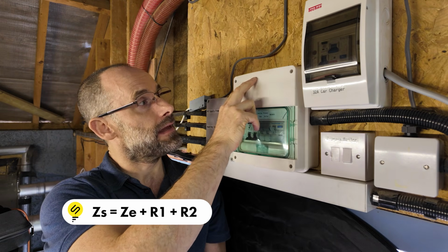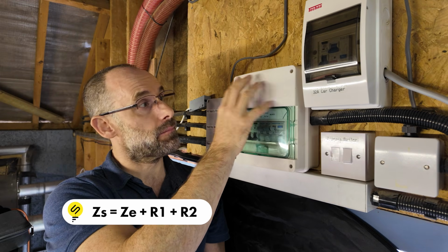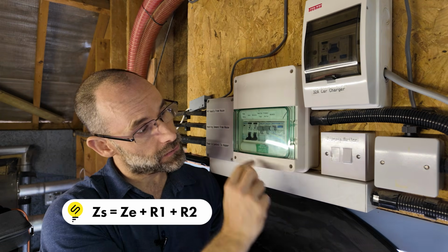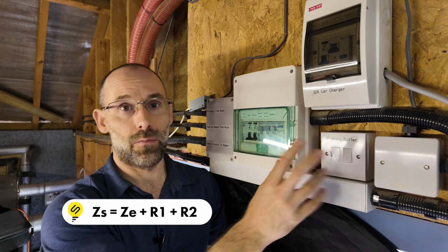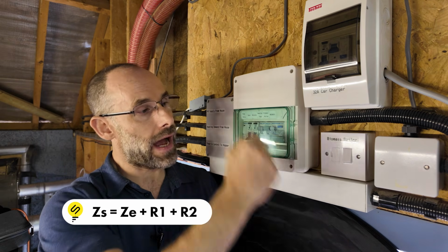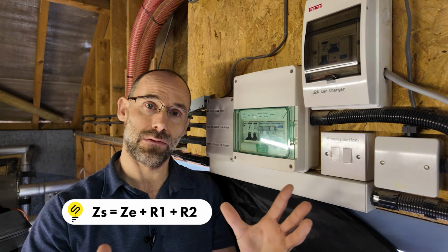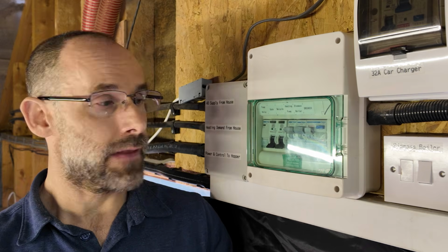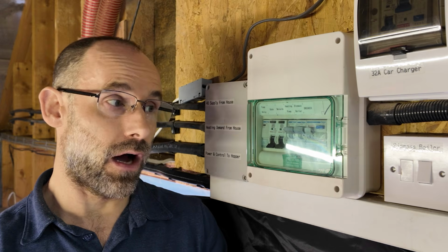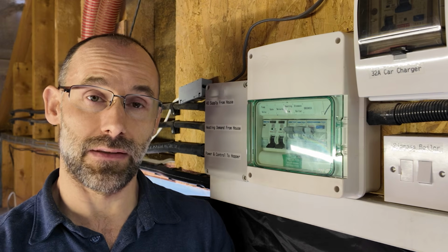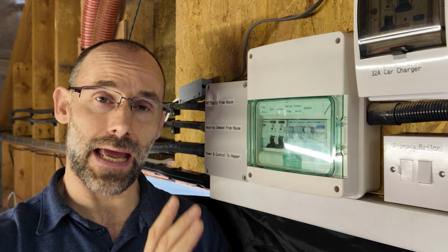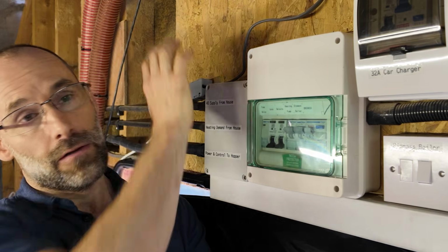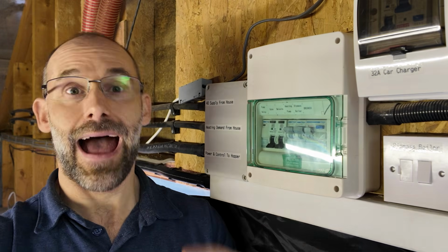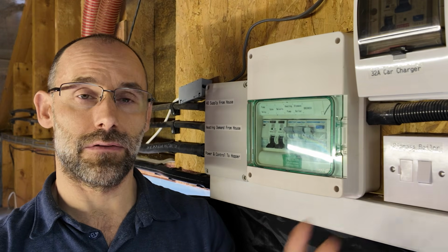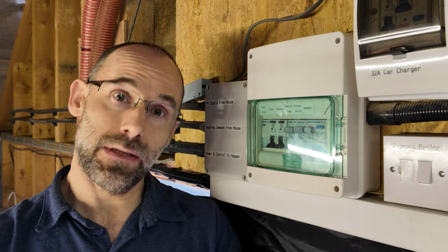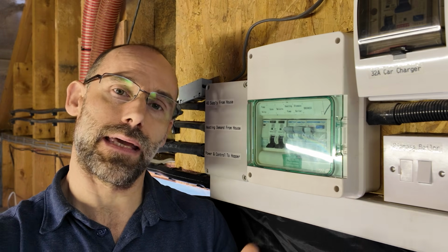Now, in theory, the ZE, the external impedance to here, plus the resistance that we measured up to this fuse connection unit, we call it R1 plus R2, if you add those together, in theory, you get this system impedance, ZS. Now you can do it by calculation, that is valid. I much prefer to measure it every time. It's a double check against these other figures that everything tallies together, that the external resistance plus the internal resistance add together to give the system impedance at the end. So it can be done by measurement, it can be done by calculation.